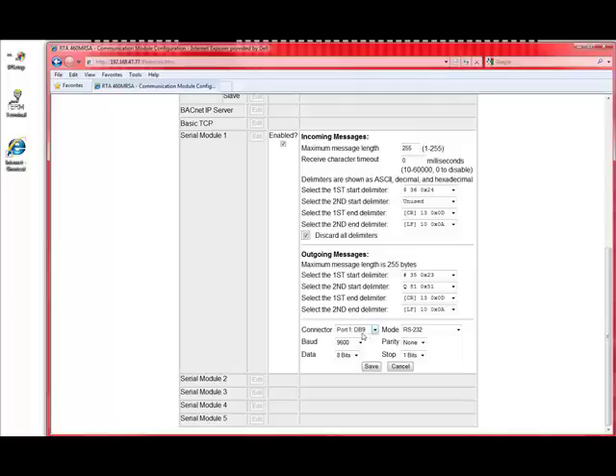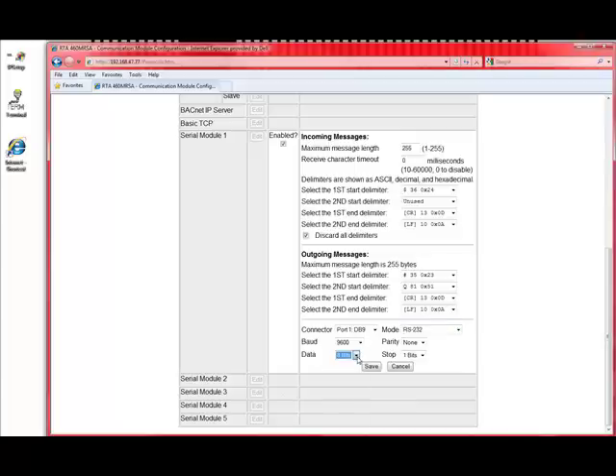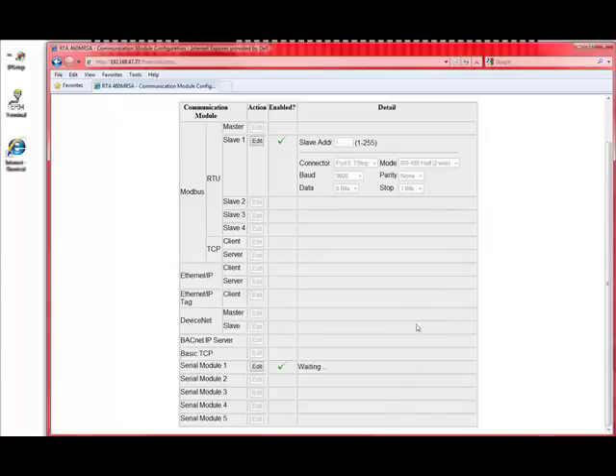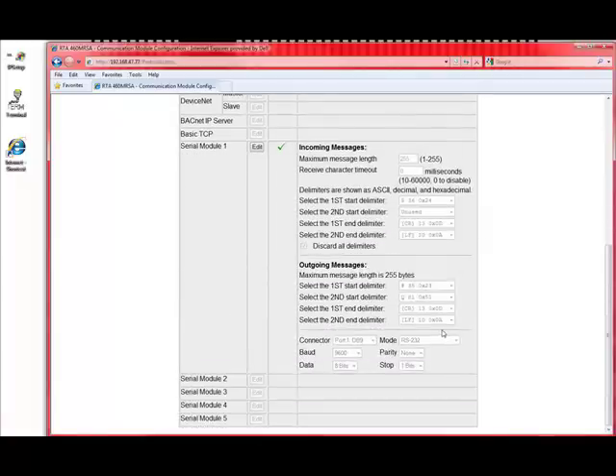Now, there's some physical aspects of the serial module we have to deal with. We're going to use the DB9 port. It's going to be RS232. We've got to set the baud rate, which is now at 9600. Number of data bits, which is 8. We're not going to use any parity. We're going to have one stop bit, and we're going to save that. So, now we've got that all taken care of. All that stuff has been locked in.